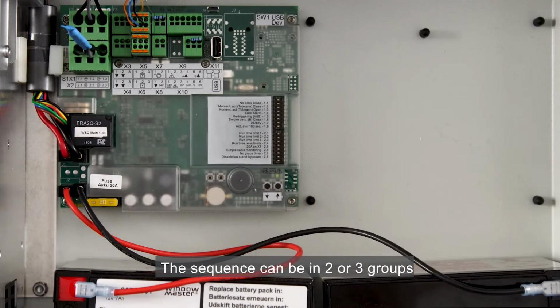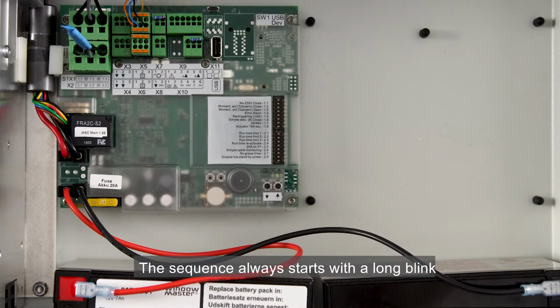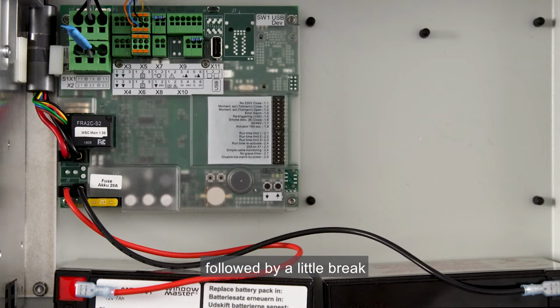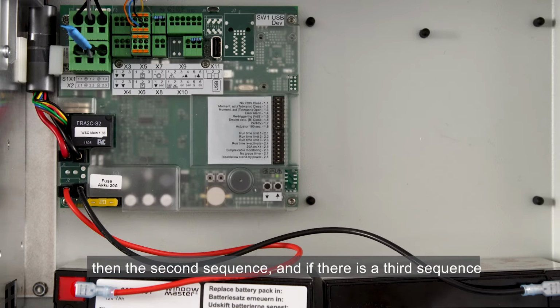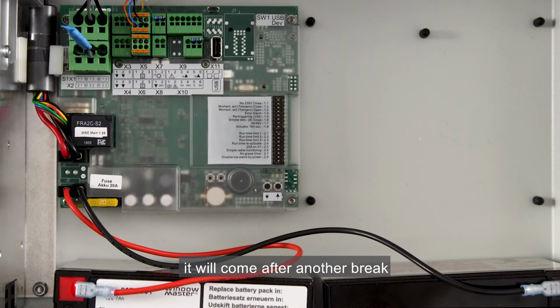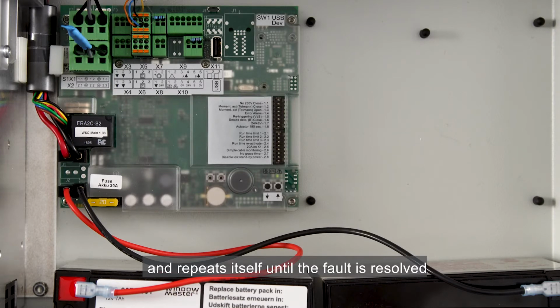The sequence can be in 2 or 3 groups. The sequence always starts with a long blink continued with the rest of the first sequence, followed by a little break, then the second sequence, and if there's a third sequence, it'll come after another break. The sequence starts again with a long blink and repeats itself until the fault is resolved.